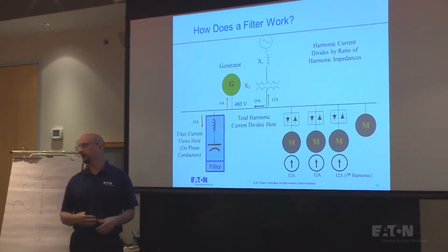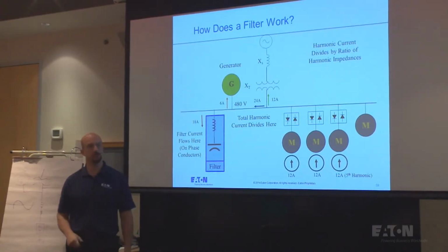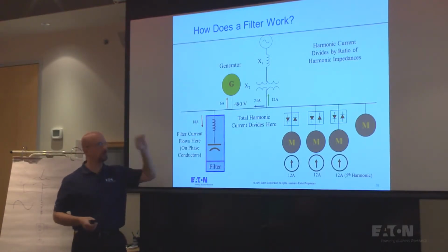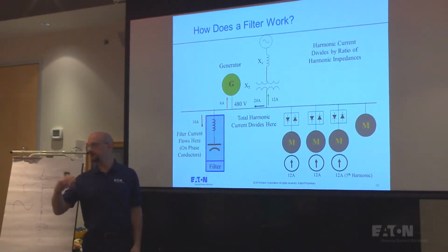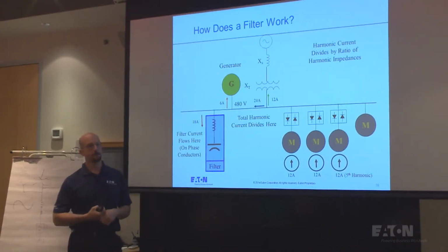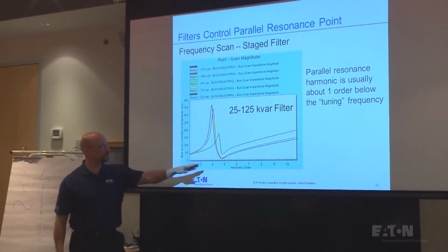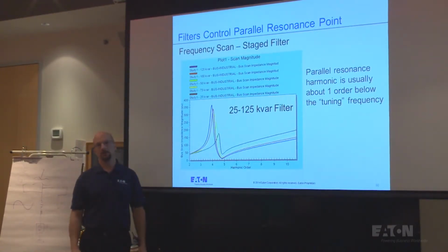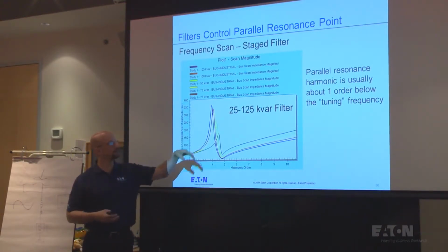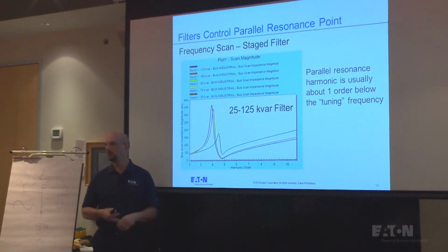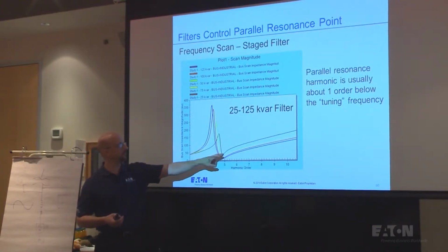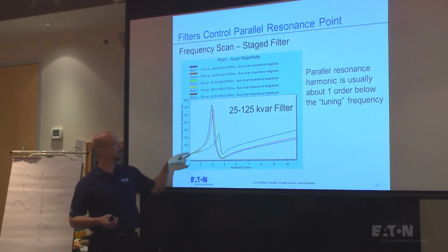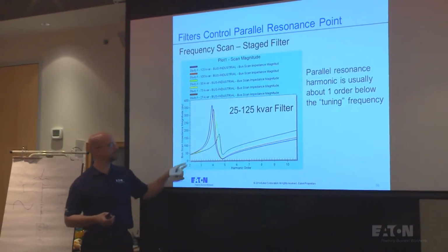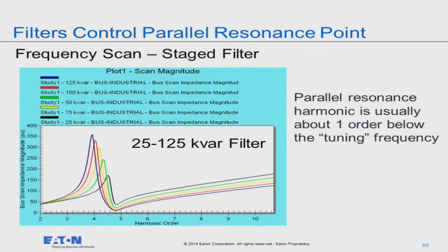By taking the current and not pushing it through that impedance, what have I effectively done? I've stopped the voltage distortion from happening. Do I have to make it a perfect filter? Does all the current have to go here? No. It just has to be less than what it would be in a normal situation. Now typically we tune these filters to something just below the fifth harmonic, because the fifth harmonic is the predominant harmonic. And this is a multi-stage filter, 25, 50, 75, 100, 125. And you can see with a small filter, the impedance, okay, is higher than with a big filter. So the bigger the filter, typically the lower the impedance.